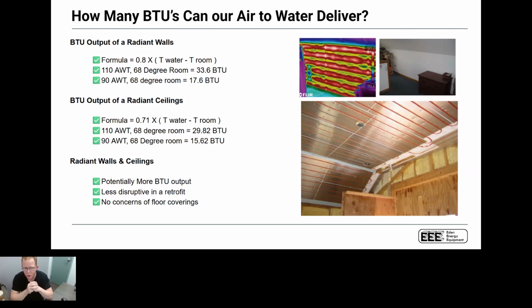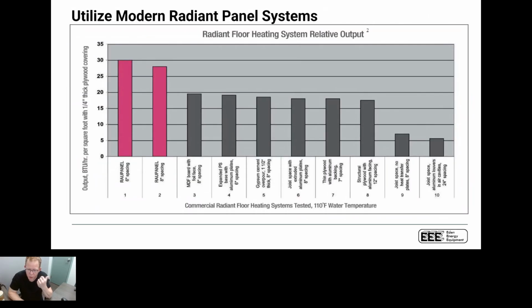But you can deliver a lot of BTUs with a very, very low temperature that's designed perfectly for an air to water heat pump. So if you remember earlier where we said 95 degrees, if we could deliver a 95 degree average water temperature, we could maintain a COP in excess of 3, so 310% efficient at the design day. Well, here's a great example of how we can do that. If we look at a 90 degree average water temperature, we can actually deliver 17 BTUs per square foot into the room, which is significant, and we want to be aware of that.